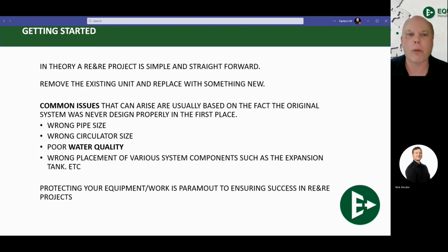So I want to talk about some of the common issues that we come across, and I kind of alluded to a few of these in the previous slide, but this is the stuff that needs to be addressed. Common issues that I see all the time, every single day, and this one I see quite literally every single day, is wrong pipe size. Wrong pipe size is almost always going to be the piping is too small.